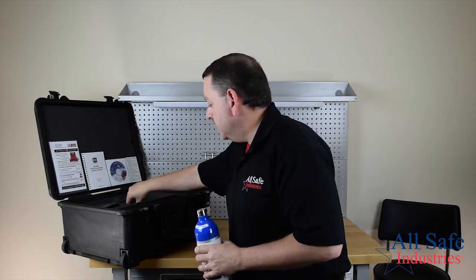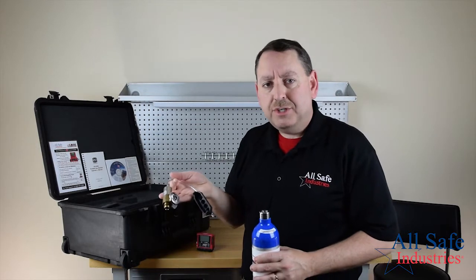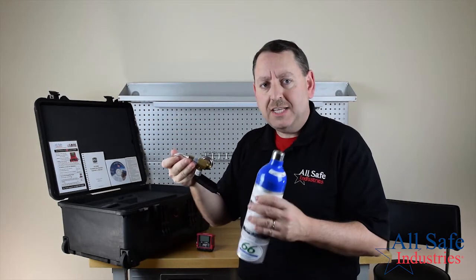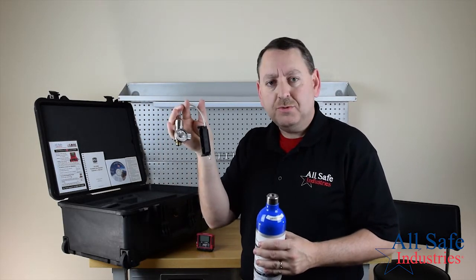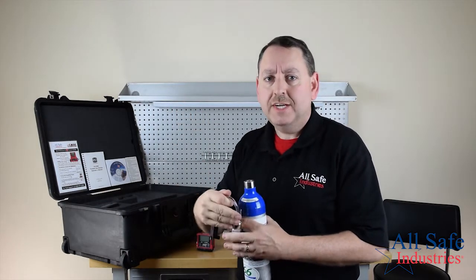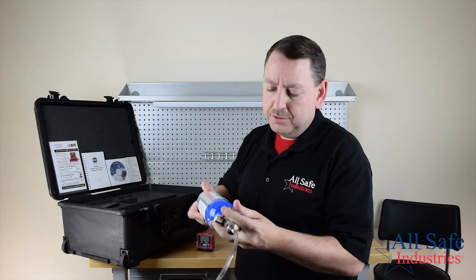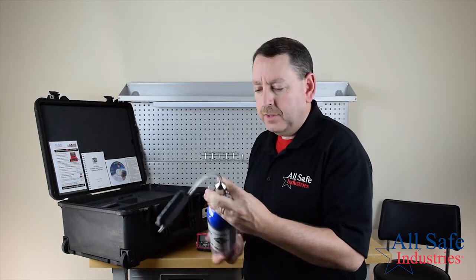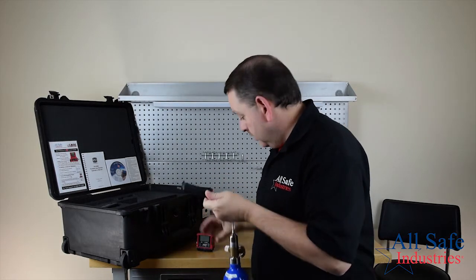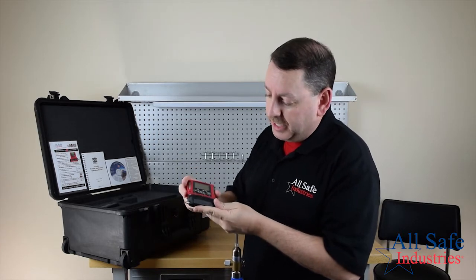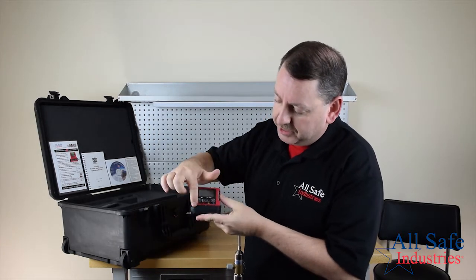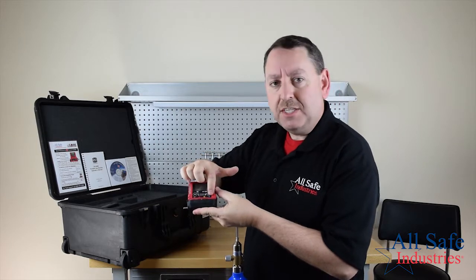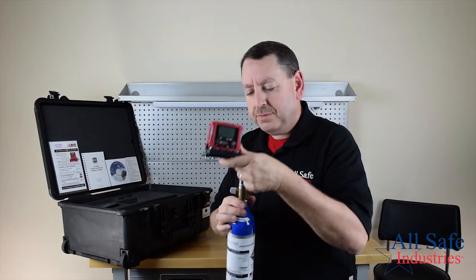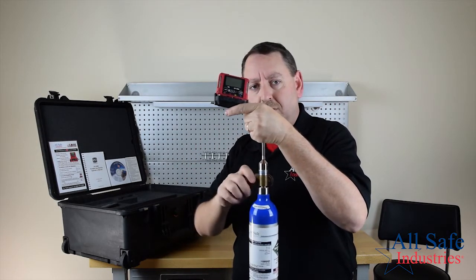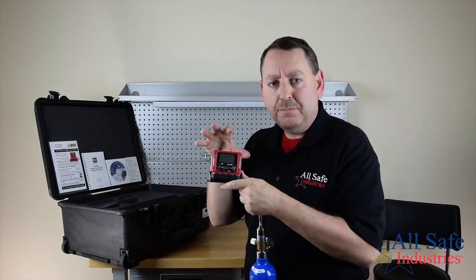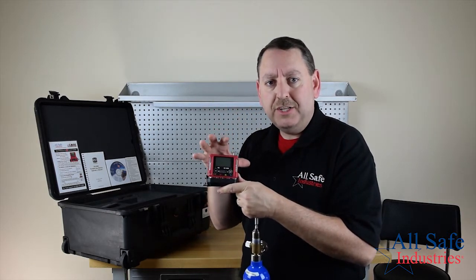The other thing you're going to need is the regulator and the calibration cup. The regulator is what flows gas out of the cylinder, and the calibration cup is what we use to make sure we feed that gas right to the sensors. So simply screw the cylinder onto the regulator, snap the instrument onto the calibration cup, matching up the names of the sensors on the cal cup with the names of the sensors on the instrument. And then you would simply turn the cylinder of gas on using the on-off knob when the meter is in calibration mode and you're ready to apply the gas.